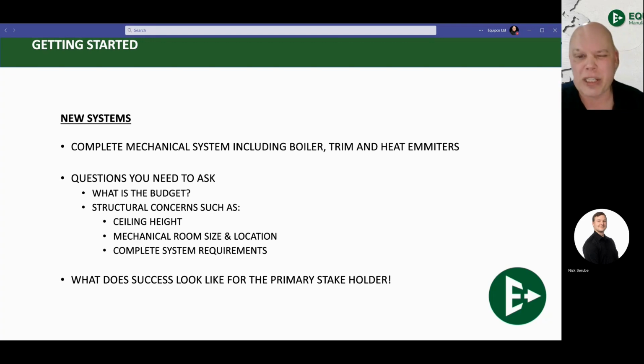But most of the time, folks don't want to see that. So where do they put the hydronic system? Under the stairs, in the basement, out of sight, out of mind, never look at it again. They give you floor space about the size of a postage stamp and expect you to put a boiler, an indirect, manifolds, radiant floor, snow melting, air handlers, all sorts of stuff down in there. You have to have that proper understanding that to get a good quality system, we're going to need a little bit of room. So make sure that they understand we're going to need more than just, you know, a 4x4 room or a little closet under the stairs. We're going to need a little bit of room to get these systems in.